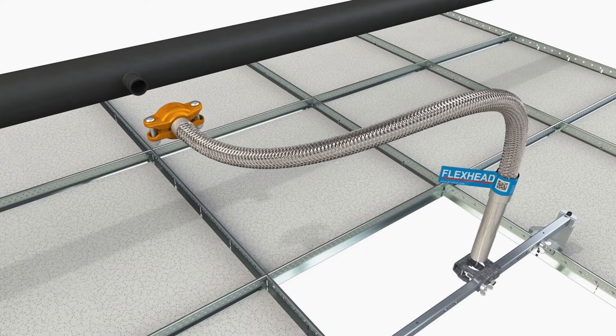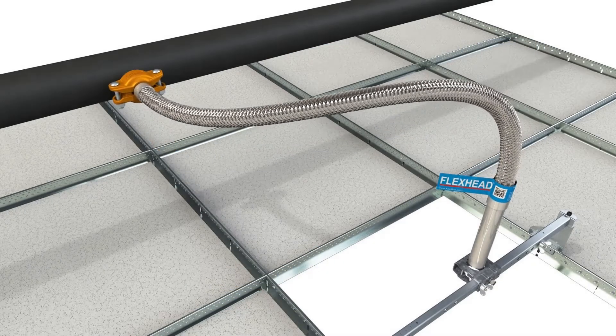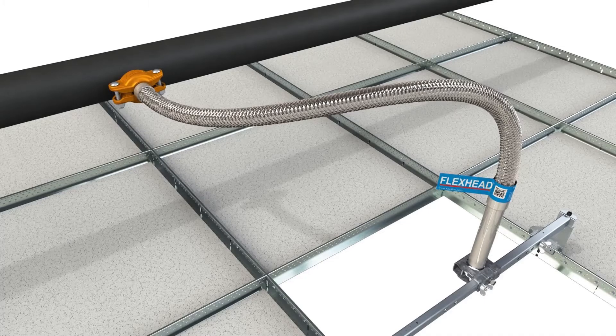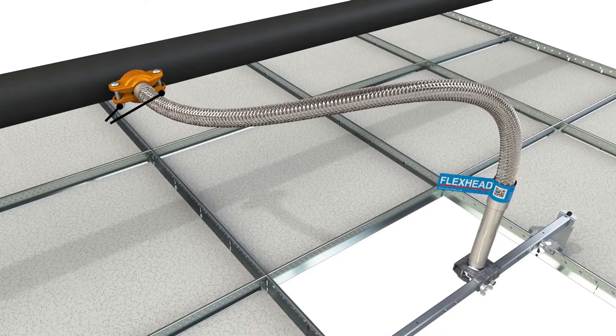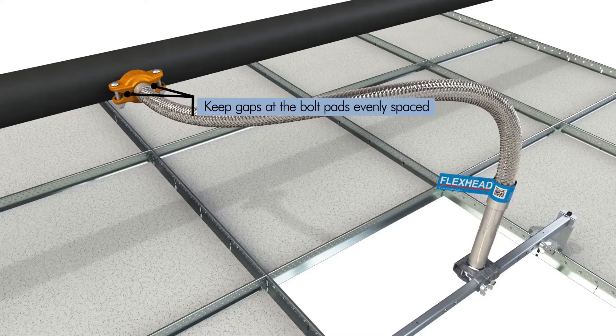Slide the Anvil SlideLok 74FP Coupling onto the weld outlet. Securely tighten nuts alternately and equally, keeping the gaps at the bolt pads evenly spaced.